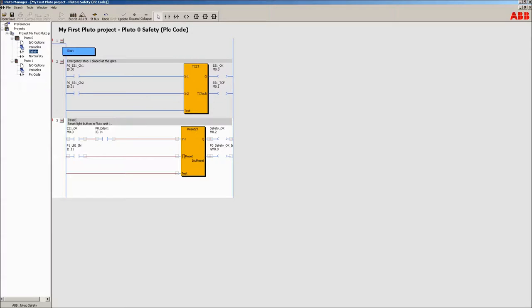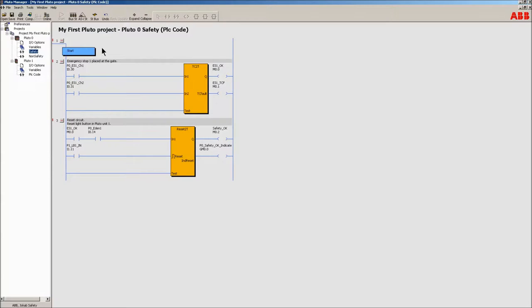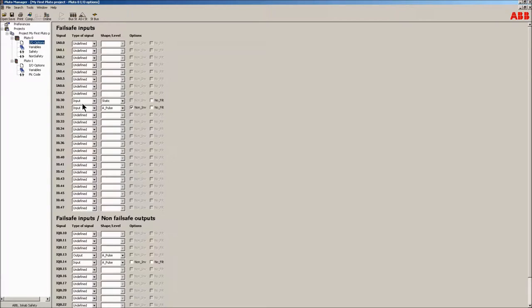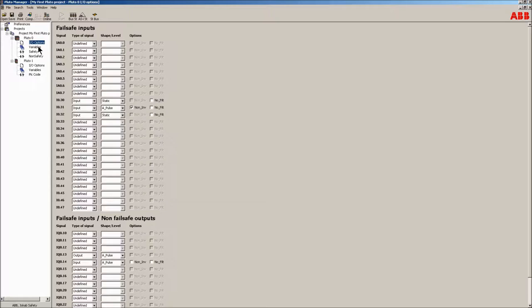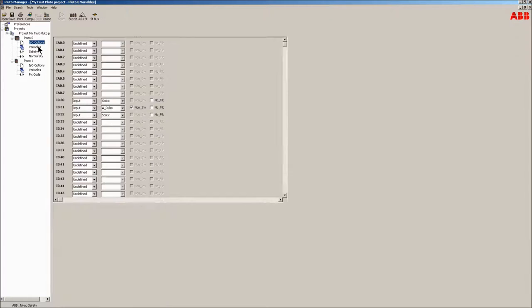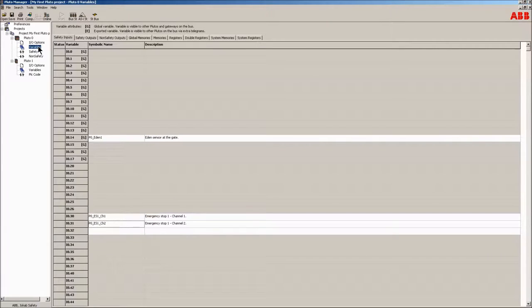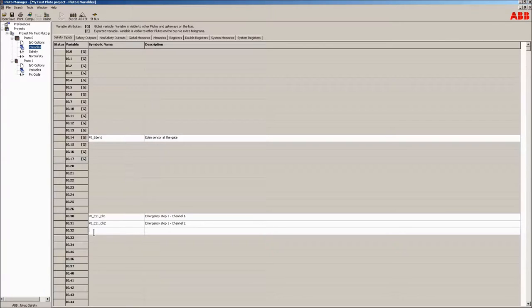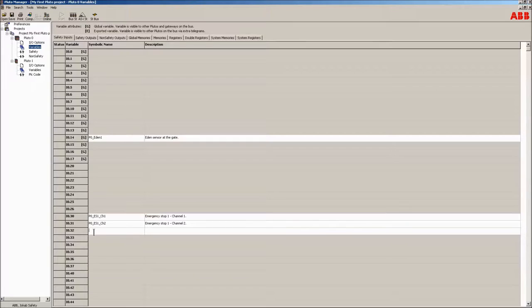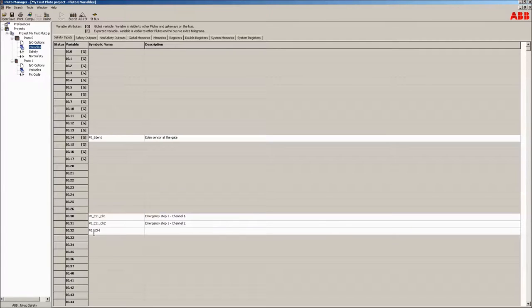To show that it's easy to add I/O later in the project, the external device monitoring signal will be added. Go to the I/O options and configure I.32 as a static input. Then go to variables and then click on the safety inputs tab. Give the input a suitable name and description, such as this input will monitor contactor 1 and contactor 2.